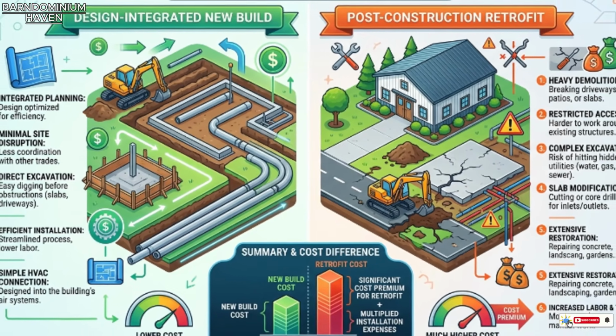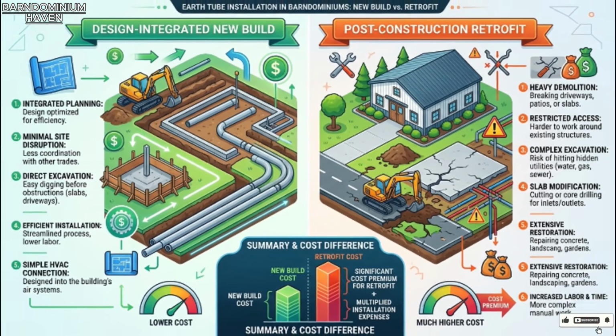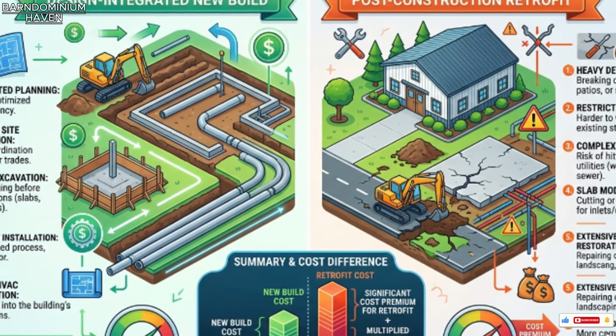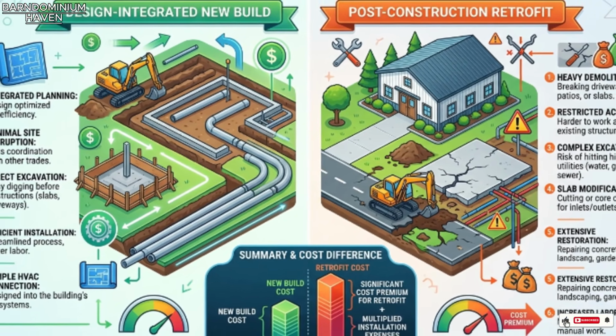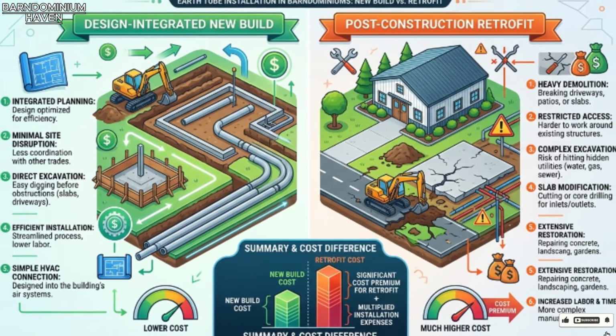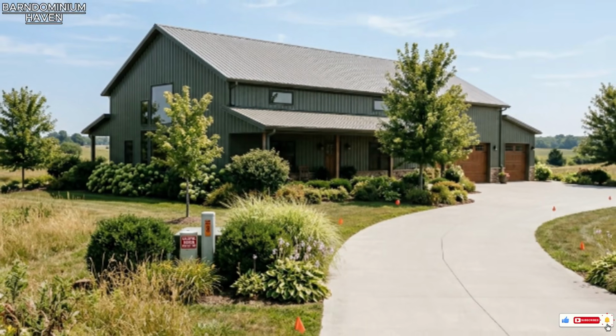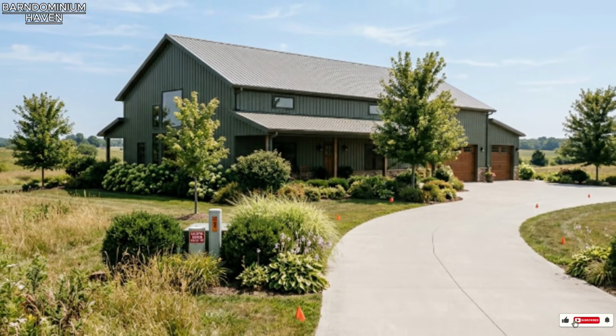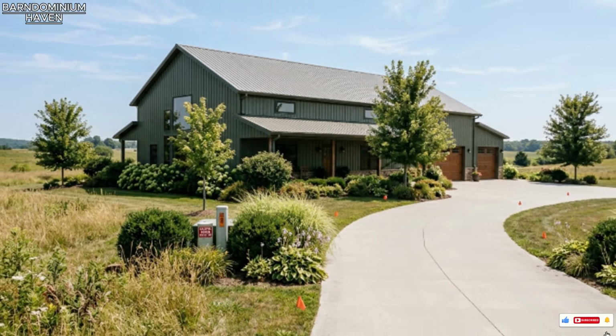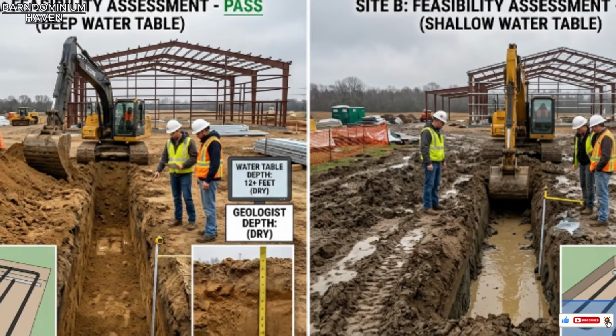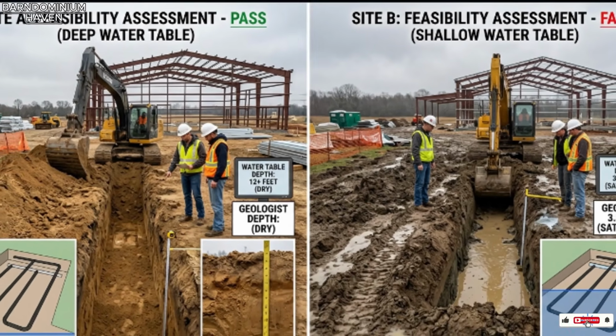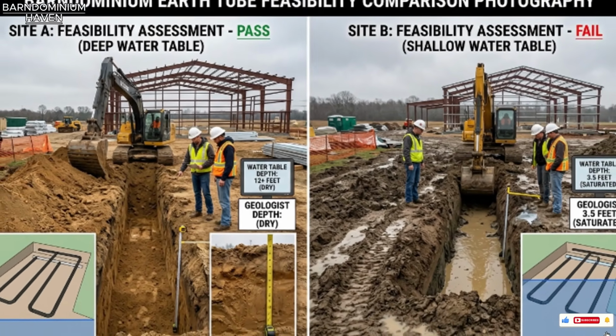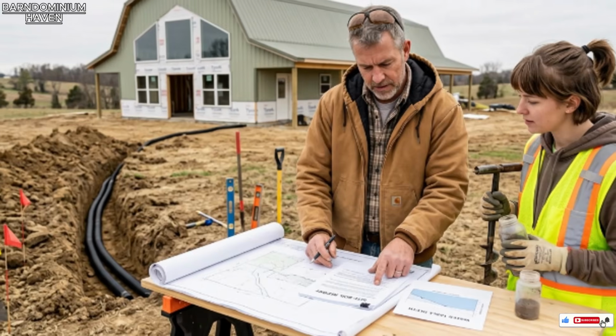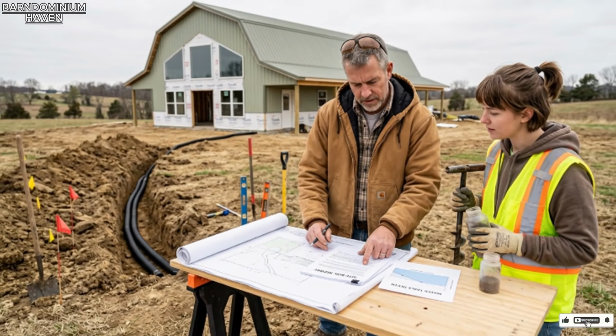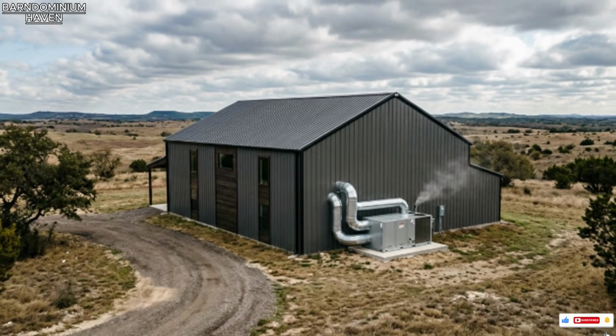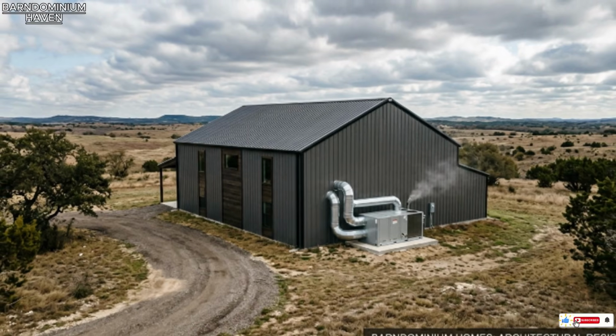And the system requires planning before the slab. An earth tube system retrofitted to an existing barndominium, after the driveway is poured, after the landscaping is established, after the site work is complete, is significantly more expensive to install than one designed into the site from the beginning. If earth tubes are part of your building strategy, they must be part of your site plan before any ground is broken.